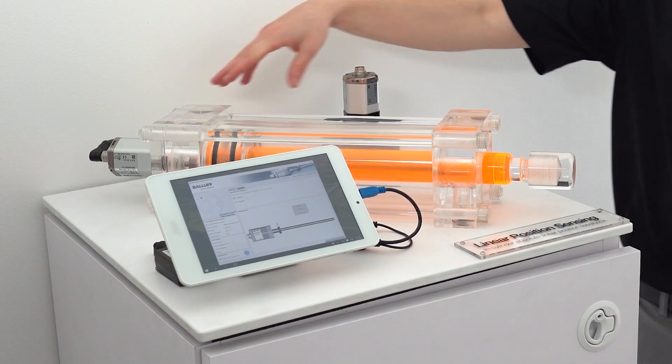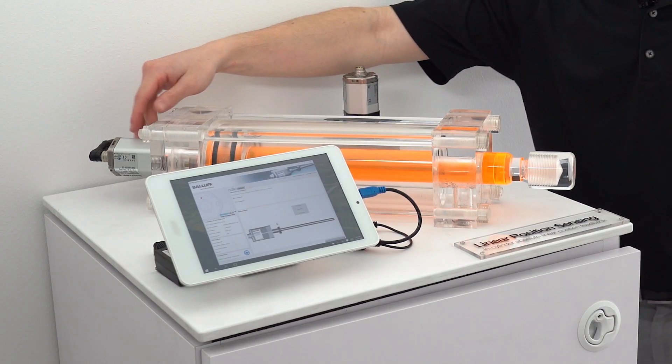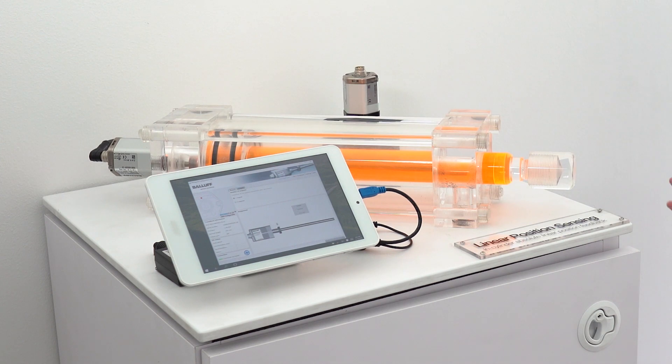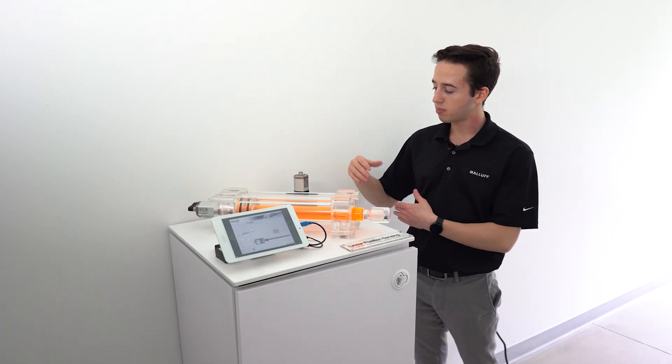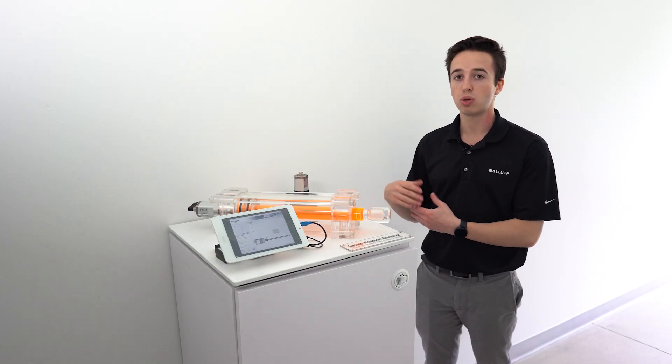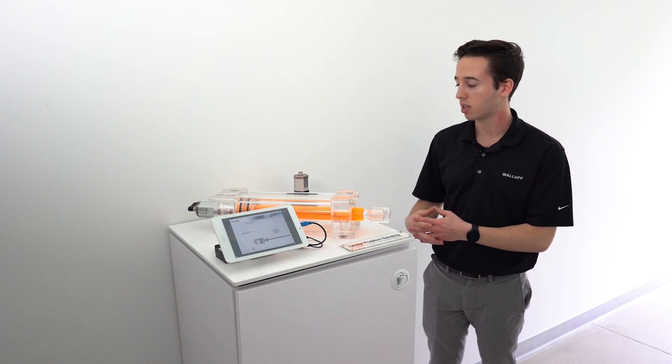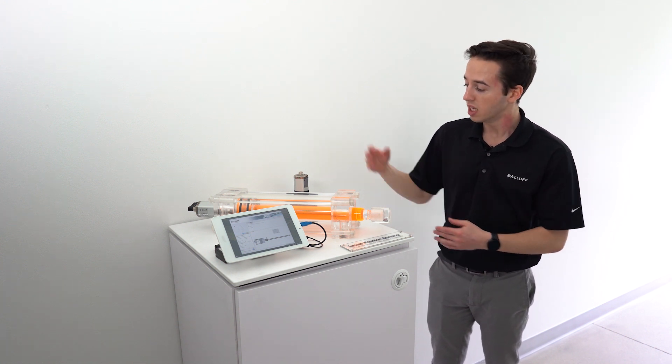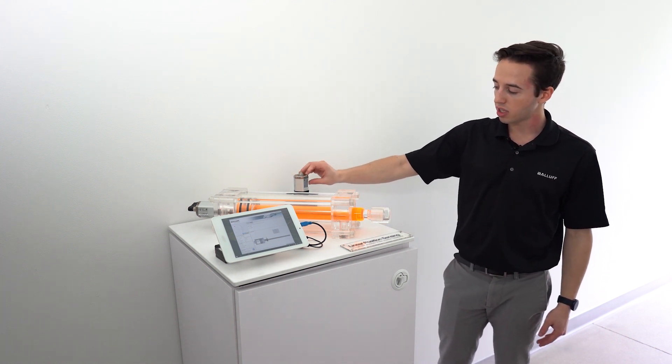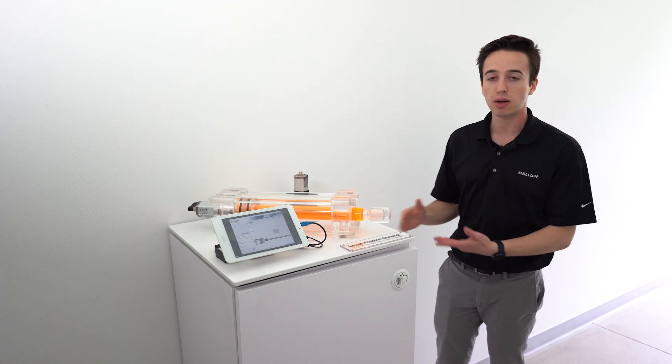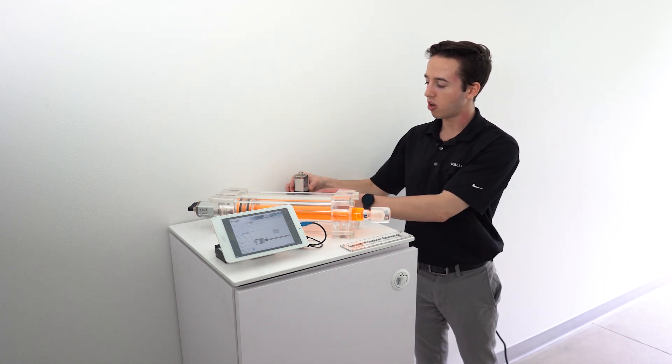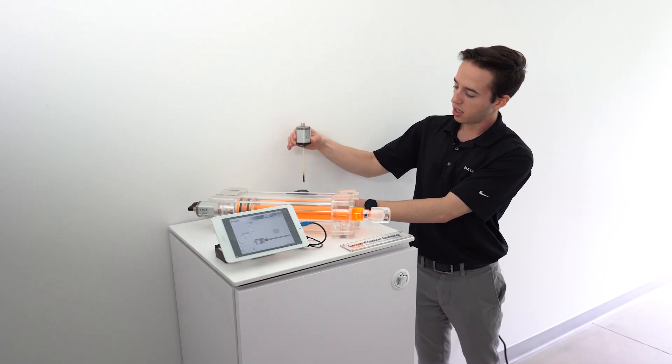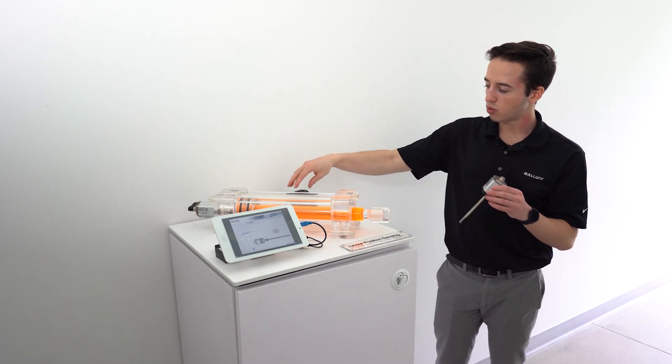Here we're showing our Z housing and one of the unique things about the Z housing is it comes in a different model that has quick replacement electronics so if something goes wrong in the electronics or the waveguide gets bent and it's not reading correctly you can actually take off the head and the waveguide and leave the rod inside the cylinder.